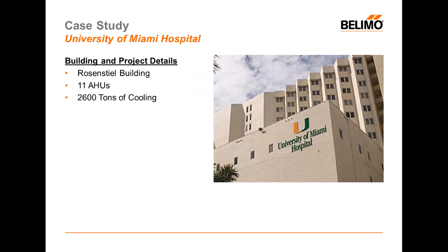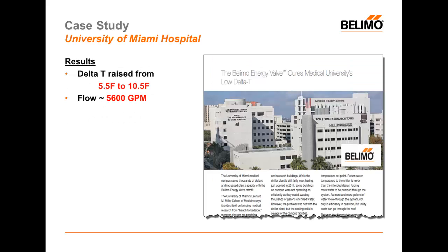Another high-profile project using the Belimo energy valve was at the University of Miami Hospital, specifically at the Rosenstiel building. Energy valves were installed on 11 air handler units encompassing about 2,600 tons of cooling. Previous to Delta-T management, they were using over 10,000 gallons a minute to serve this 2,600-ton load, and the average Delta-T was 5.5. After implementing Delta-T management, the Delta-T was raised from 5.5 to 10.5 degrees Fahrenheit, and flow was reduced down to about 5,600 GPM.